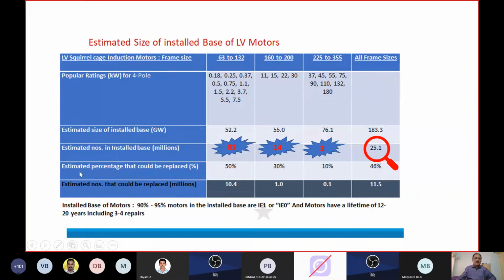And the estimated percentage that could be replaced as given by NMRP is 50% of these motors which are below IE1 or non-IE motors. Around 30% of this population can be replaced with IE3 or IE4. Similarly, 10% of this population can be replaced. Difficult to replace this population because these are costly motors. So payback estimates could be very low. So based on that, approximately 1 crore 15 lakh motors are available for upgrade to IE3 in our country.